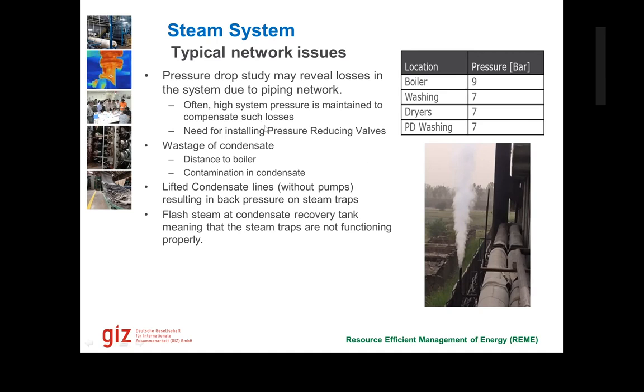Pressure, we keep on increasing pressure to compensate for these losses, but it's better to install pressure reducing valves. Then wastage of condensate takes place. You remember this in the textile case story on day 2. We saw that this company did not install a condensate recovery system because this machine was very far away from the boiler. This is a true case I have seen many times.